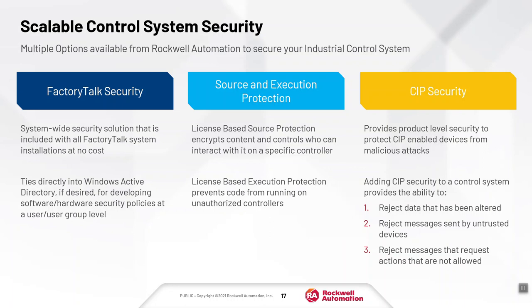We've also got another layer of control system security called Source and Execution Protection. This is a license-based solution: with Source Protection, we can encrypt the content and control who can interact with content specific to a controller. You can also leverage license-based Execution Protection to further secure a given asset and prevent code from running on unauthorized controllers. For example, if you're an OEM who deployed a ControlLogix solution to an end user, that runtime would only run on that specific controller and not be downloadable or runnable on any other controller globally.